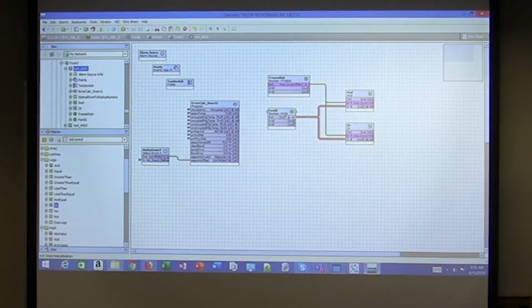what does null mean? Means he doesn't want to have an opinion. So null means kind of no number. I'm not sending you anything. I'm releasing you away. Null will accept the absence of a number. NaN is not a number. So null is what you set it to when it's okay if it's not going to be used. No opinion. So because this is an AND block, and I'm not sending it a value, I'm releasing it to whatever it wants to be, this went true.